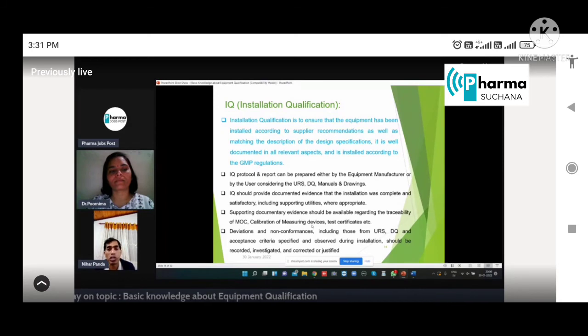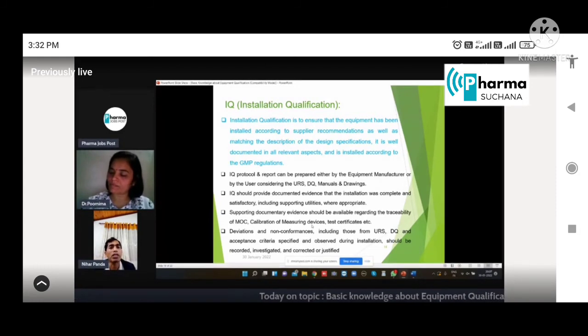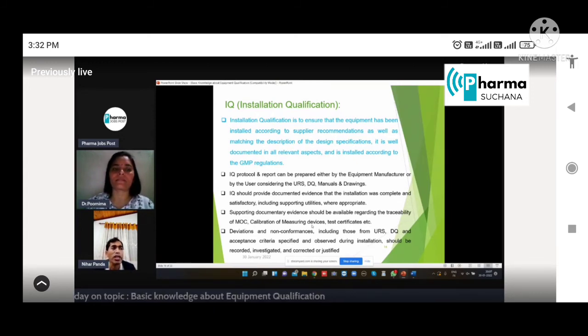Through the IQ protocol. The IQ protocol and report can be prepared by the equipment manufacturer, if the vendor is providing; then it's okay. If they are not providing, it can be prepared by the user department, considering the URS, DQ, equipment manual, and other drawings. IQ should provide the documented evidence that installation was complete and satisfactory, including supporting utilities wherever appropriate.